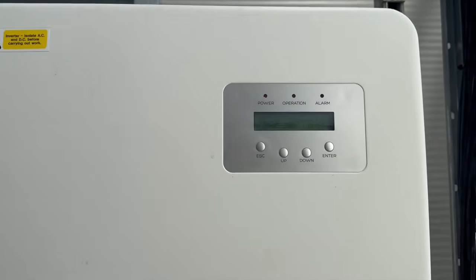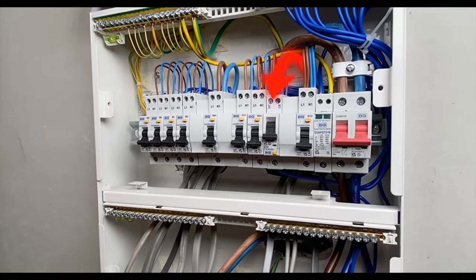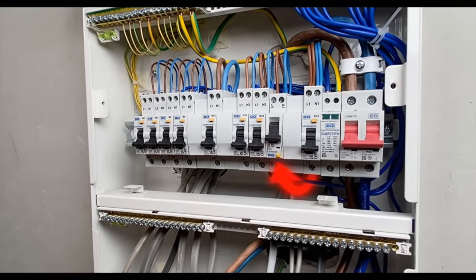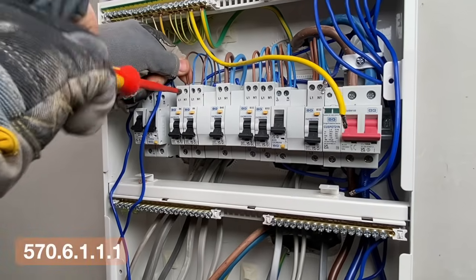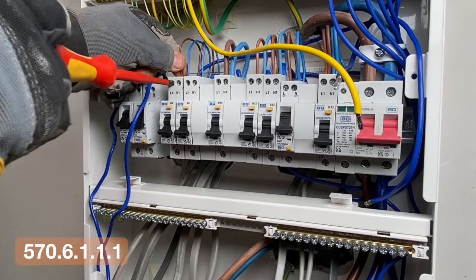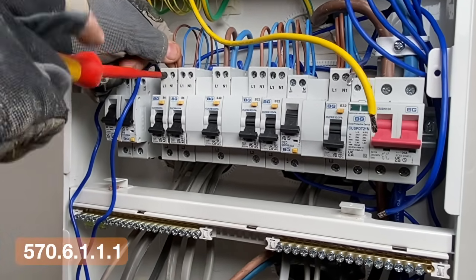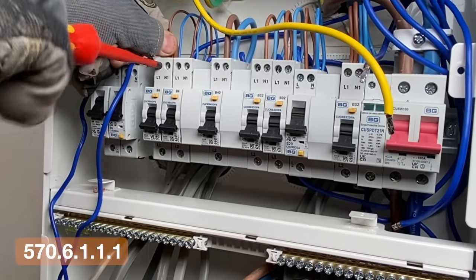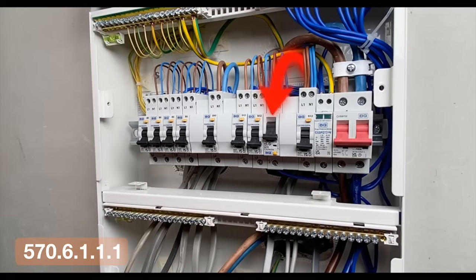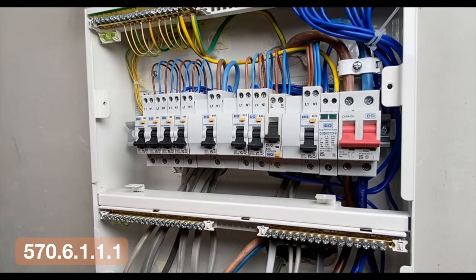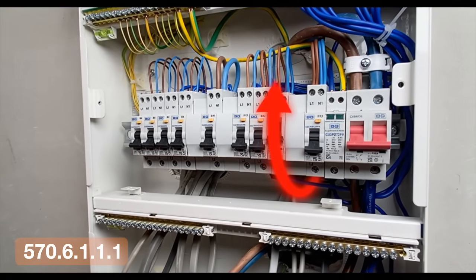This is the equipment that controls the energy flow, and that flow can be in both directions, which then affects protection. Regulation 570.6.1.1.1 requires that bidirectional protective devices are selected where appropriate, so protection must operate correctly whether energy is flowing into or out of the installation. RCD selection is also affected.